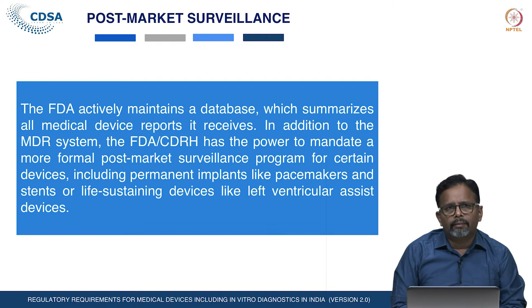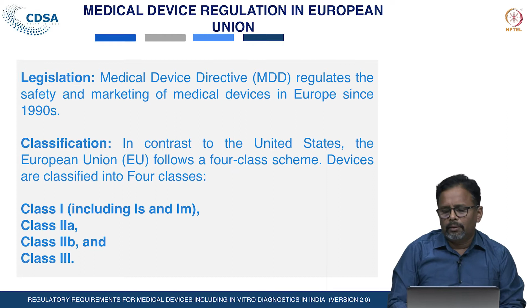Europe is based on the medical device directive. The medical device directive has regulated the safety and marketing of medical devices in Europe since the 1990s, and in Europe also the devices have been classified into 4 different classes based on the risk of the devices. Class 1, that includes class 1S or class 1M, where class 1S is considered sterile, and class 1M includes class 1 devices having a measuring function for measuring certain parameters. Class 2A devices are low to moderate risk, class 2B devices are moderate to high risk, and class 3 devices are high risk devices. These devices have been classified based on risk as per the medical device directive or the diagnostic directive.